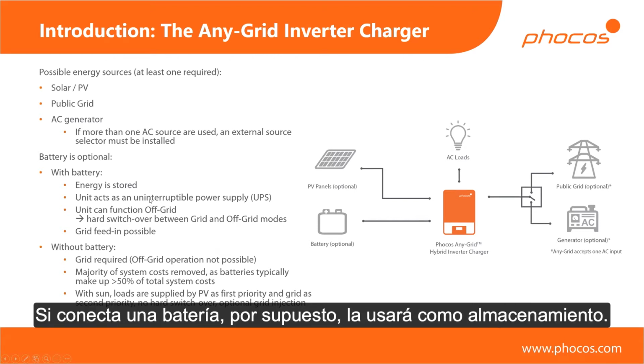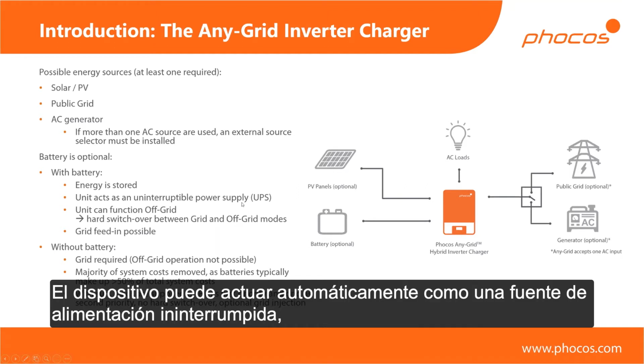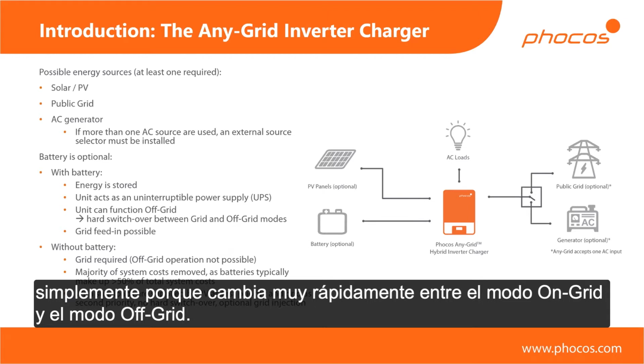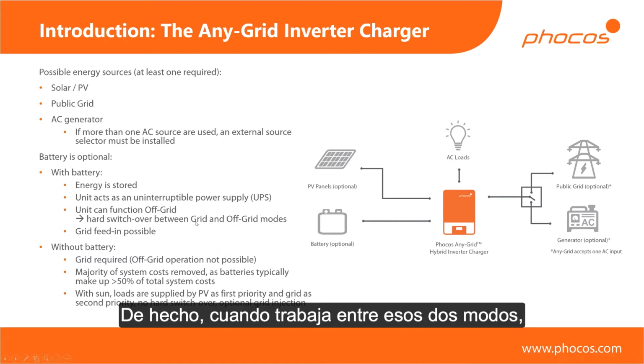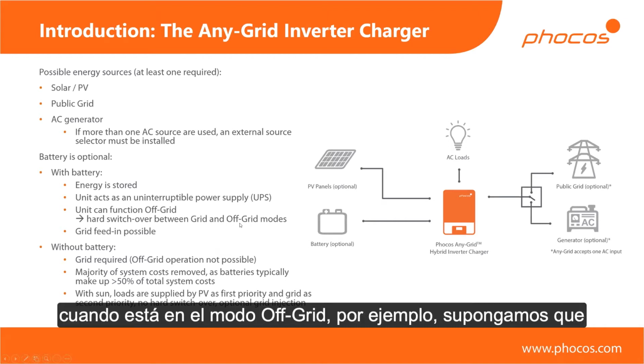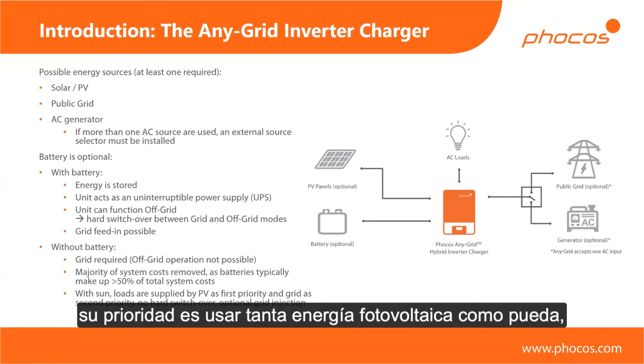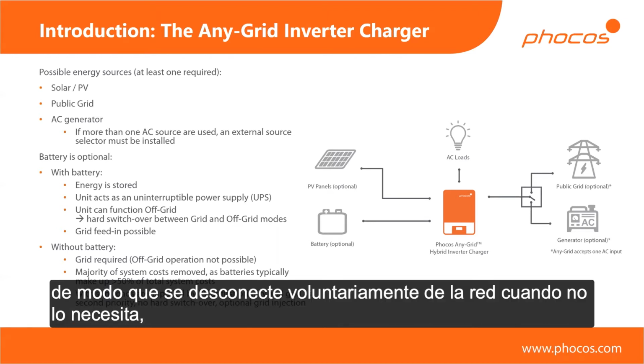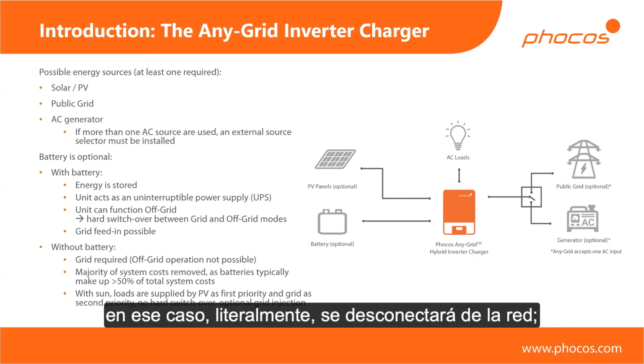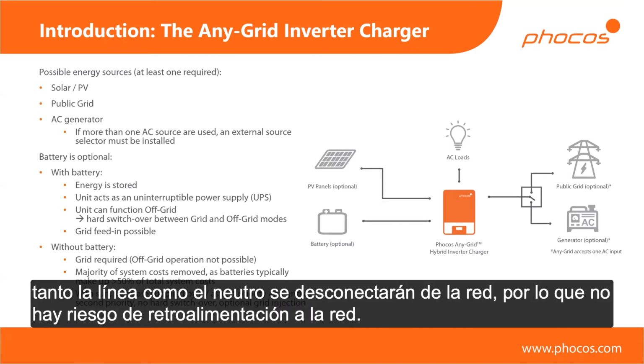If you do connect a battery, then of course you use that as storage. The device can automatically act as an uninterruptible power supply, simply because it switches over so quickly between grid mode and off-grid mode. And when you're in off-grid mode, for example, let's say your priority is to use as much PV energy as you can, so you want to voluntarily disconnect from the grid when you don't need it. In that case, you will literally be disconnected from the grid. Both line and neutral will be disconnected, so there's no risk of backfeeding into the grid.